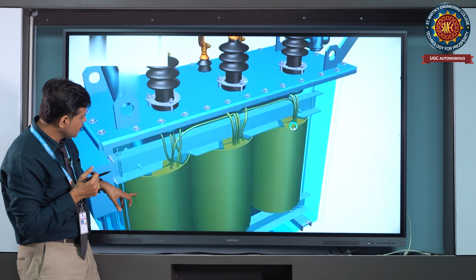This is the core of your transformer. Any observation? These cores have what are called concentric windings. What is a concentric winding? The entire winding is placed on the limb. This is called concentric winding. How is this winding placed? First, the LV winding is near the core and the HV winding is on the outer part. Why is the LV winding near the core? Because low voltage requires less insulation. The HV winding is placed outside, with some distance for the insulation.